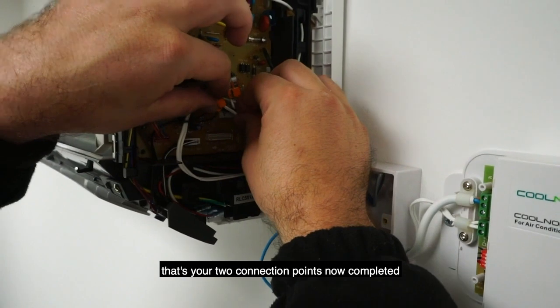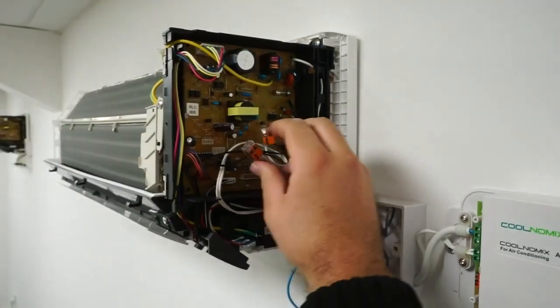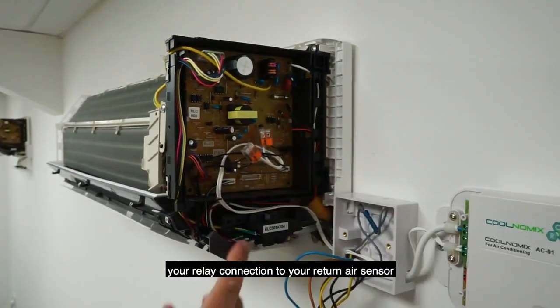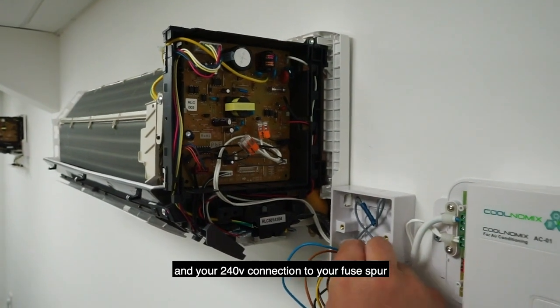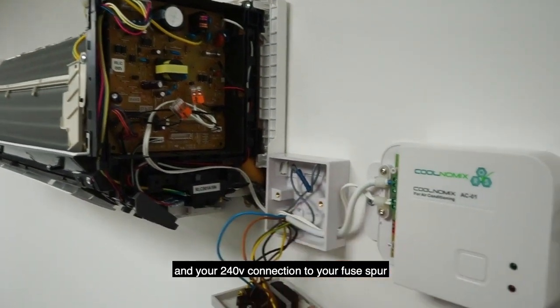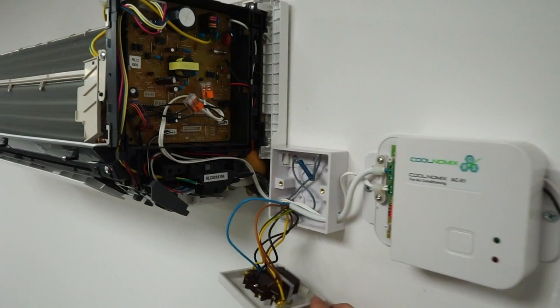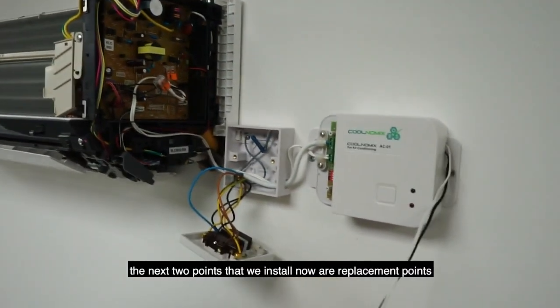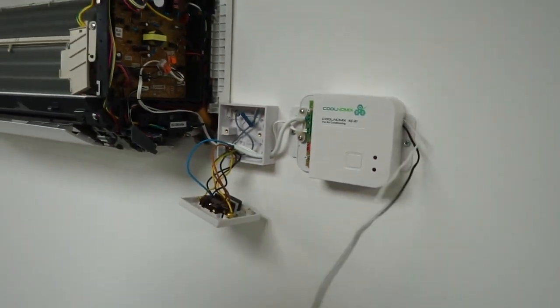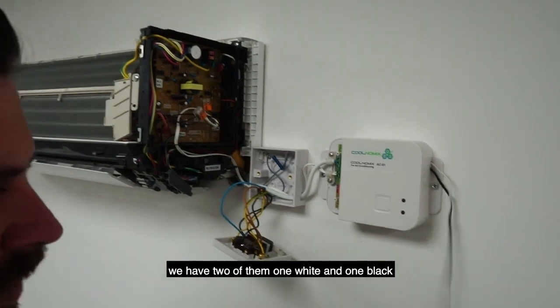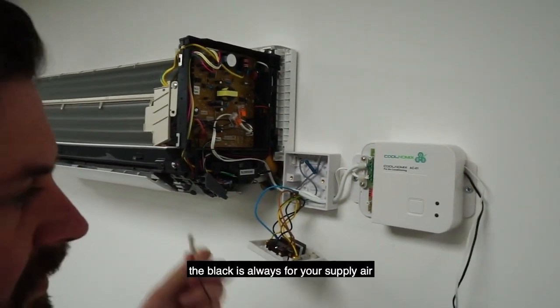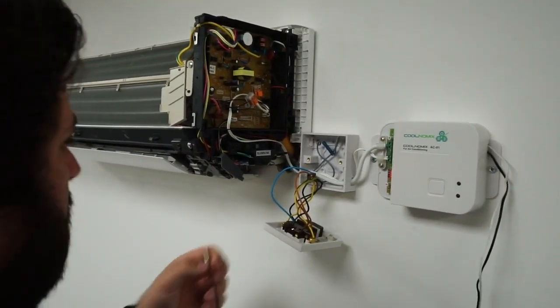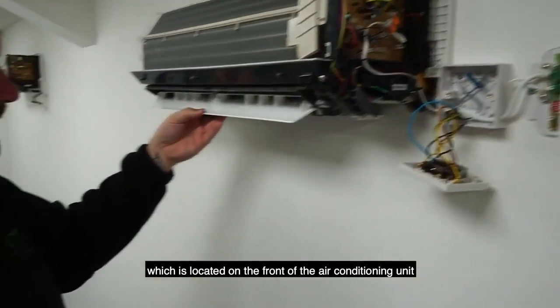Okay, that's your two connection points now completed. Your relay connection to your return air sensor and your 240 volt connection to your fuse spur. The next 2 points that we install now are replacement points. We have two of them, one white and one black. The black is always for your supply air, which is located on the front of the air conditioning unit.